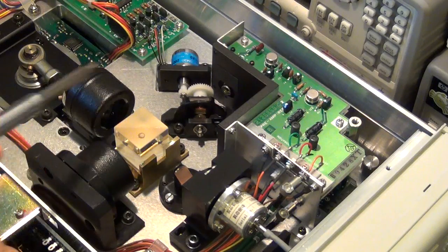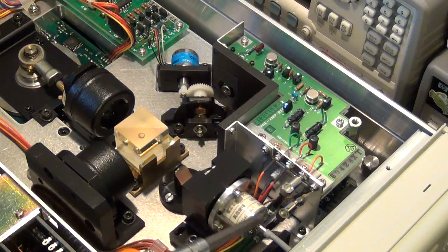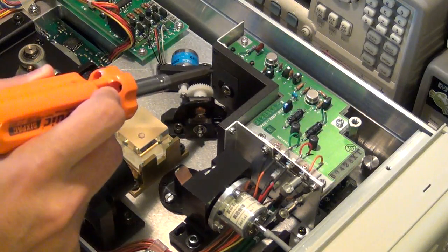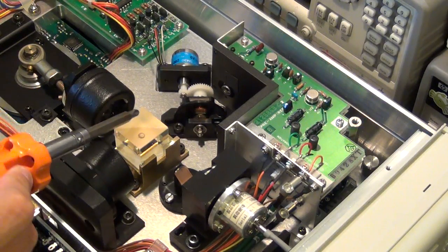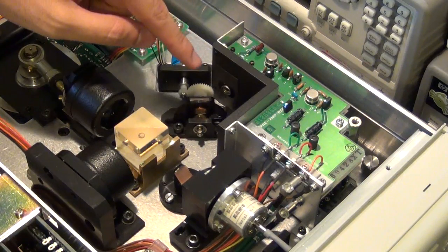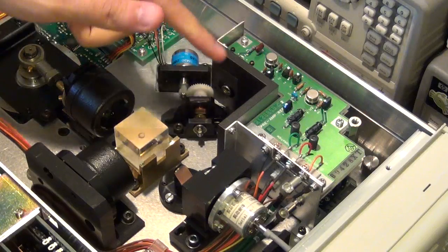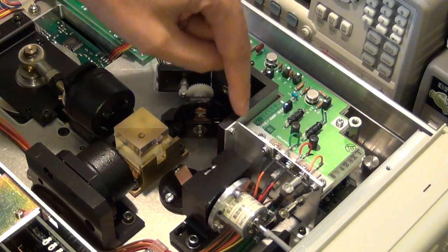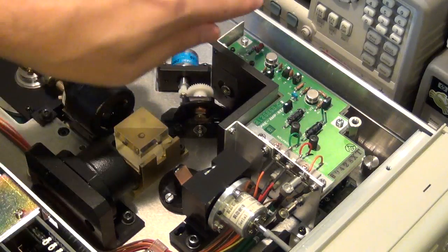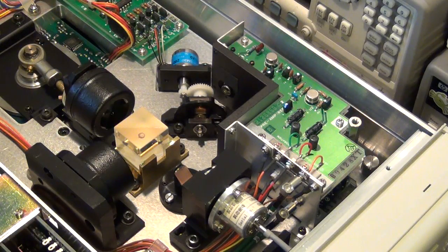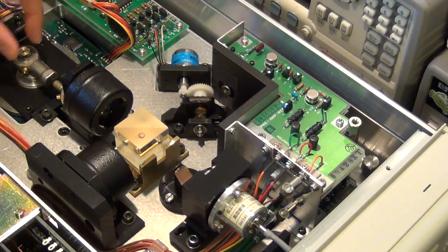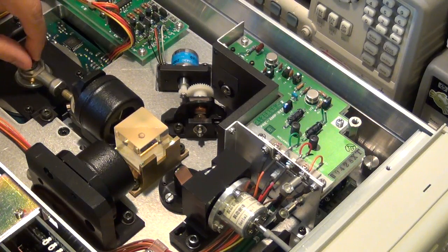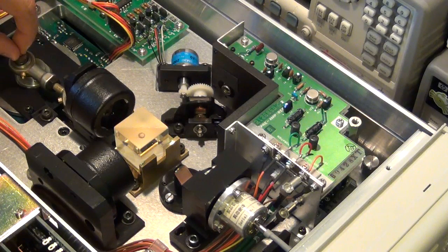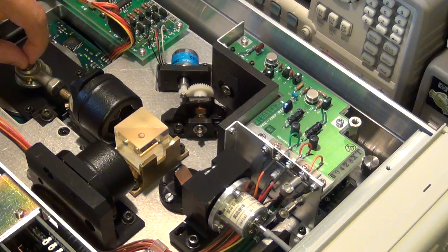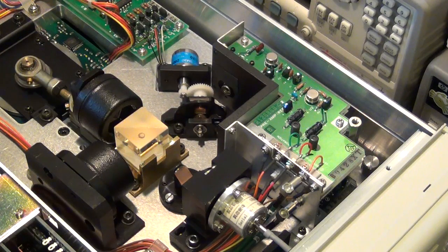I'll give you a close-up view of all of this, but just so you have a bird's eye view right now. So light comes in here, bounces against this mirror, goes through the detector, or goes through, bounces this mirror, comes back here, goes through the detector. And the fringing pattern can then be measured on the different type of sensors that you have. So here is the deep infrared sensor. The light goes this way for the deep infrared sensor, it goes that way for the near visible red colors. But this mirror moves like this with this motor. So this mirror can move back and forth, which then allows you to adjust this distance precisely in order to control the fringing pattern, which is then a function of wavelength. So let me turn this thing on.